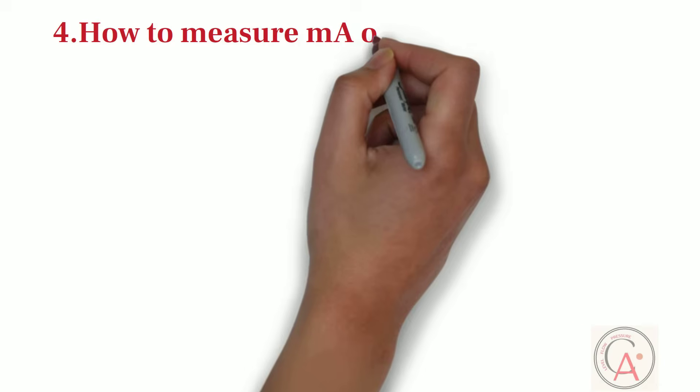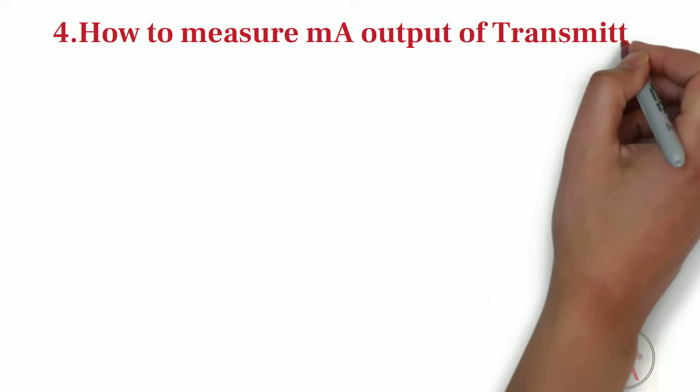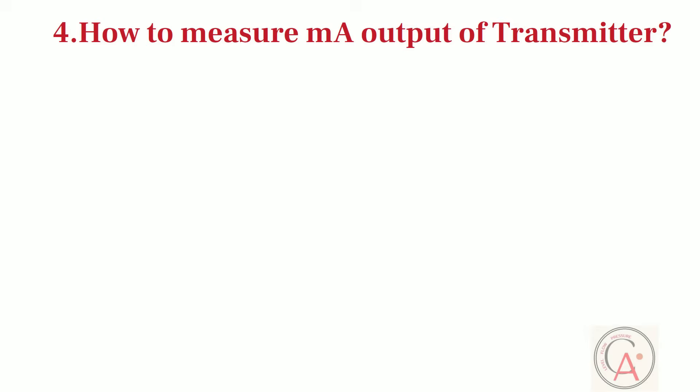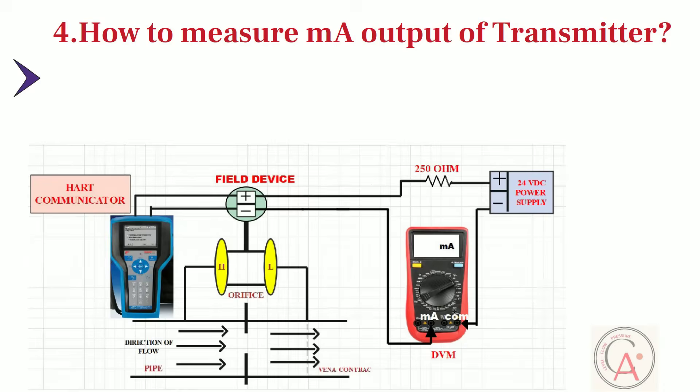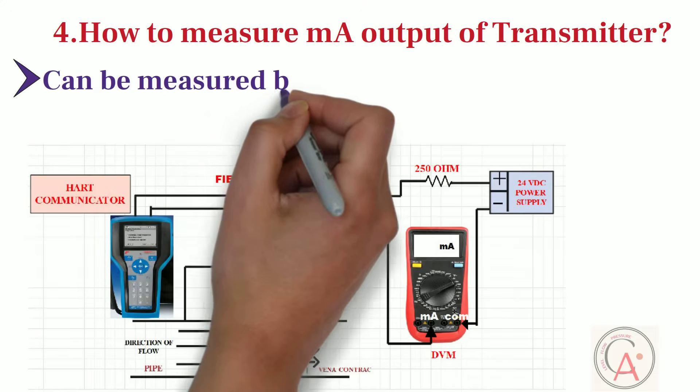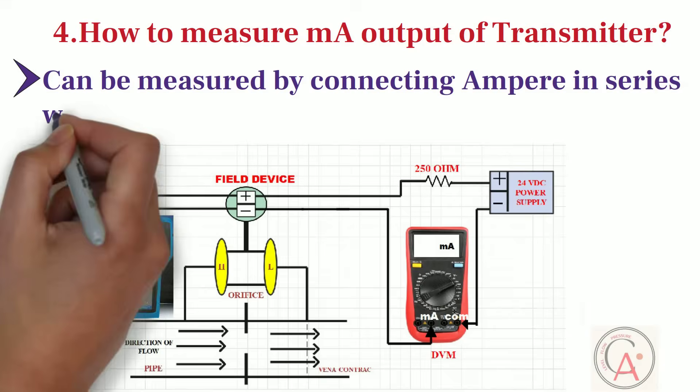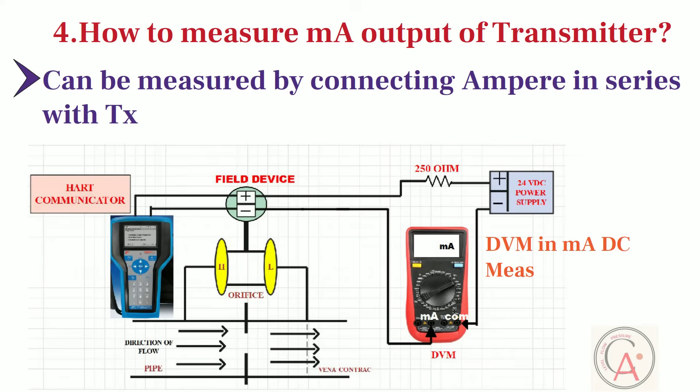Fourth common type of question is, how to measure milliampere output of transmitter. Milliampere output of transmitter can be measured by connecting multimeter in series with transmitter and putting multimeter in DC milliampere measuring mode.